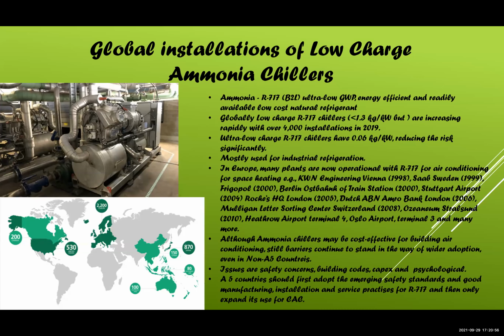And therefore, in Europe, particularly for heat pump applications for space heating, ammonia has been used in public buildings, and not just industrial refrigeration, but even in public buildings. And I've given loads of examples, including airports, London Airport, Oslo Airport. I happened to be there on the day of the Oslo Airport inauguration with ammonia. All our RTAP members were taken for a visit, and we visited one of the largest ammonia heat pumps in the world. At that time it was being inaugurated for providing space heating in Oslo Airport. That was a long time ago, about 25 to 30 years ago. Now these things have changed.